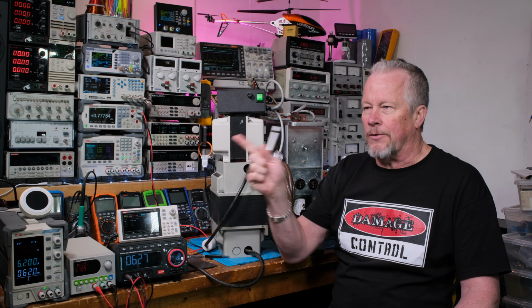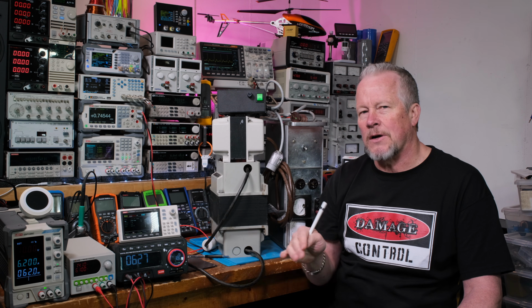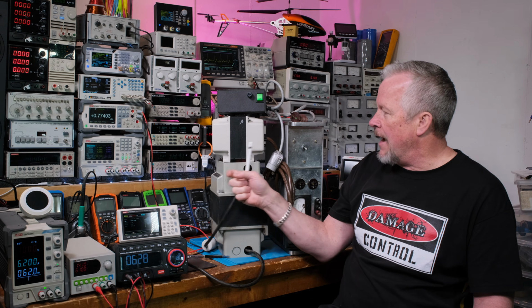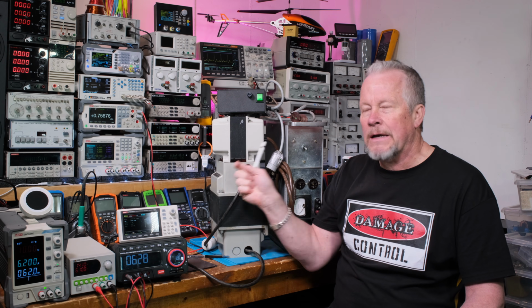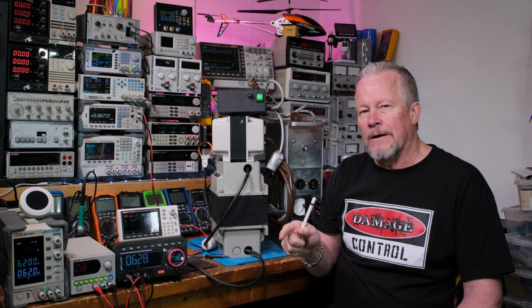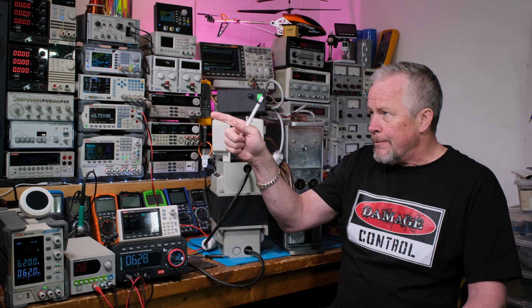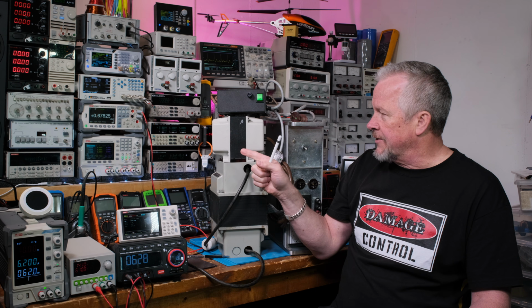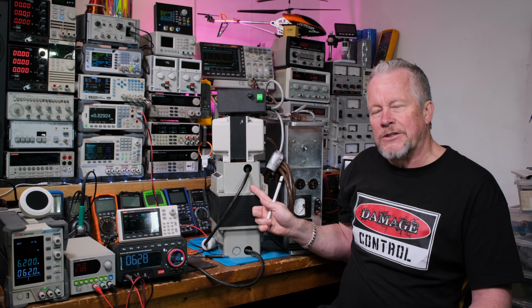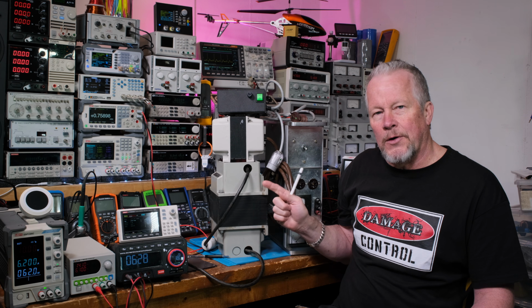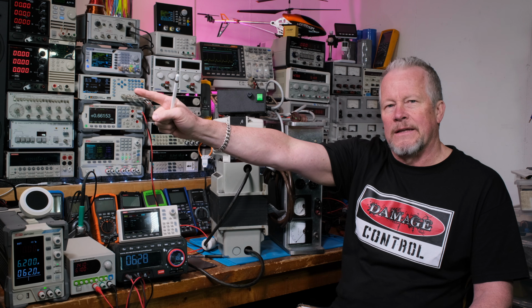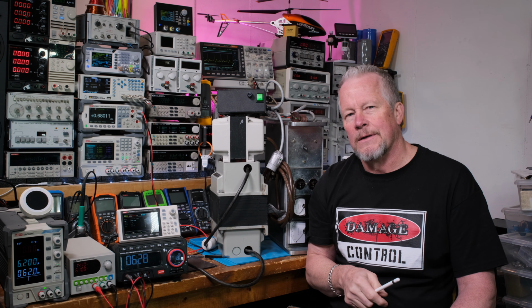That's a much better grounding system. It's also called safety ground, because now if the line touches the metal, there's a fault current. The current comes from the line conductor into the chassis, into the green wire, the third conductor, and back to the breaker, and pops the breaker.